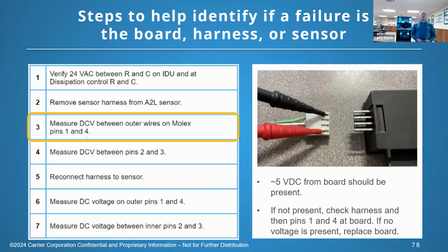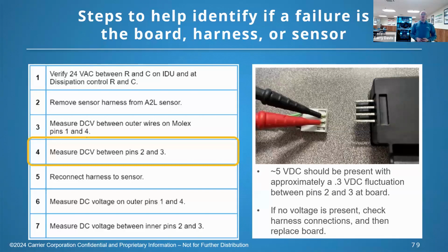Measure the DC volts on that harness between pins 1 and 4. Should be about 5 volts DC. If it's not present, check it back at the board. Do you have a broken wire in your harness, or is the board not producing the DC voltage? Measure on your inner pins. With the sensor disconnected, should be about 5 volts, very minimal fluctuation between those 2.